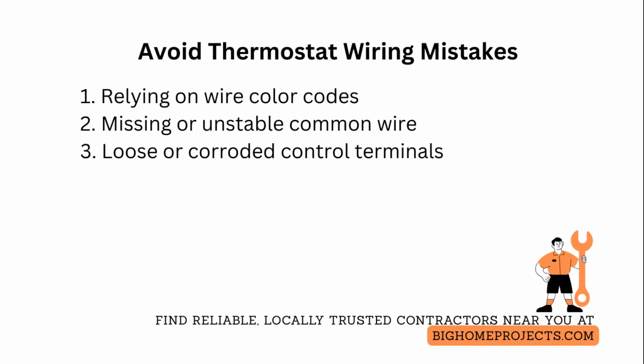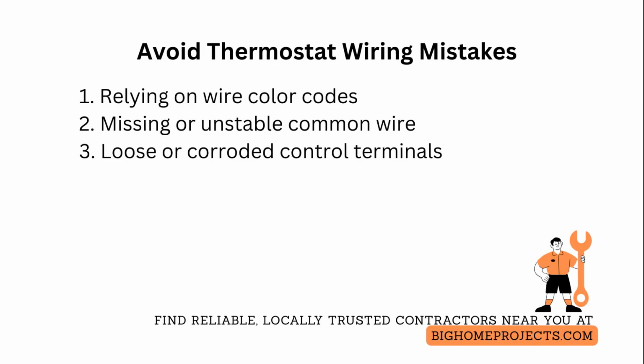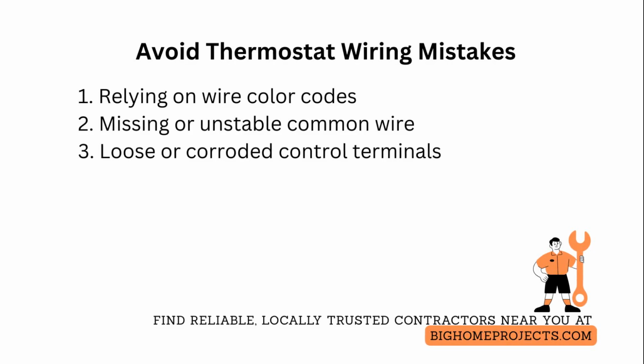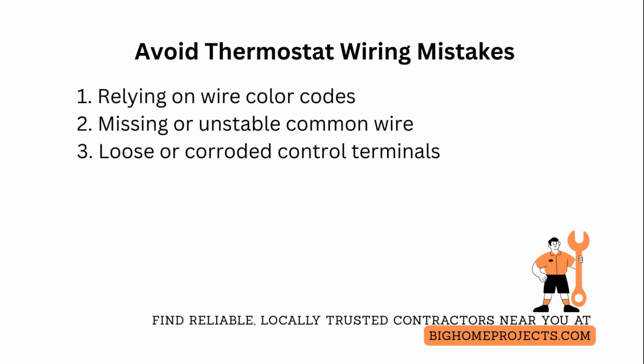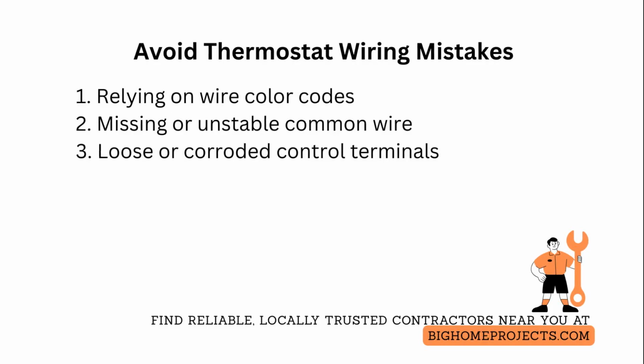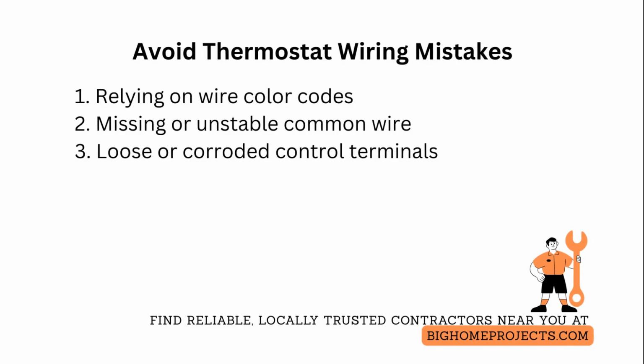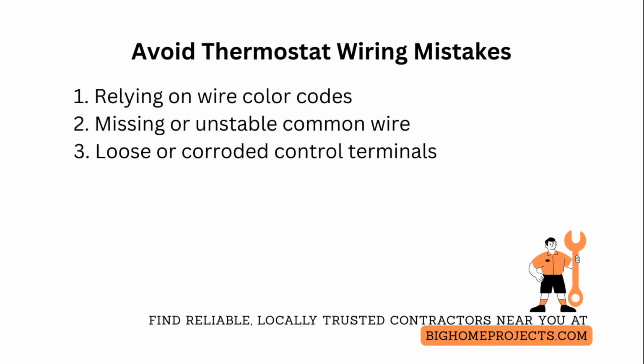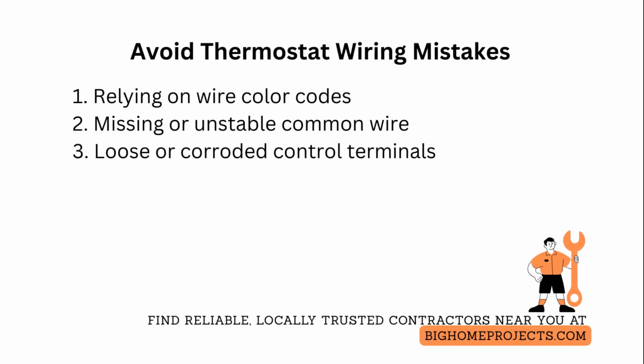One of the most frequent thermostat wiring mistakes is relying on wire color codes instead of verifying control board terminal designations, which causes incorrect connections and shorted circuits. Fix this by opening the unit, reading the board's silk-screened labels, and tracing each conductor to its terminal with a meter. One of the common issues is missing or unstable common wire connections that prevent smart thermostats from powering up. Resolve this by locating a proper common on the control board, testing transformer output voltage, and if necessary, installing a compatible transformer or common maker kit while checking transformer load limits.